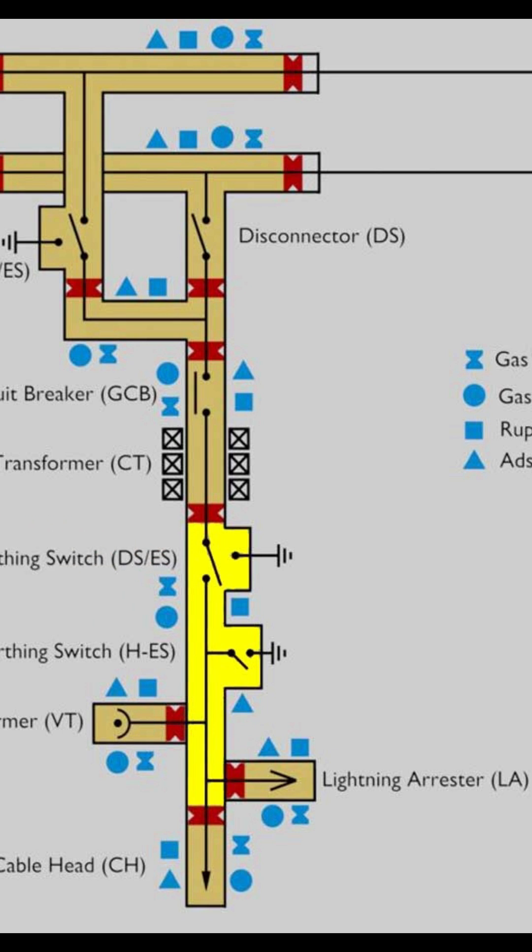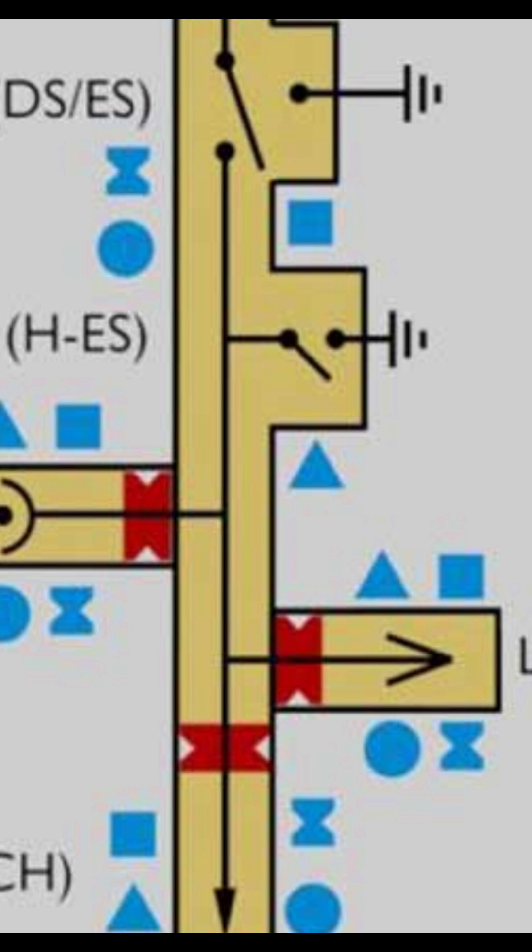Here you see there are two earth switches. There will be another earth switch called a high-speed earth switch. This is required to discharge the trapped charge of the cable very quickly. This is another compartment.